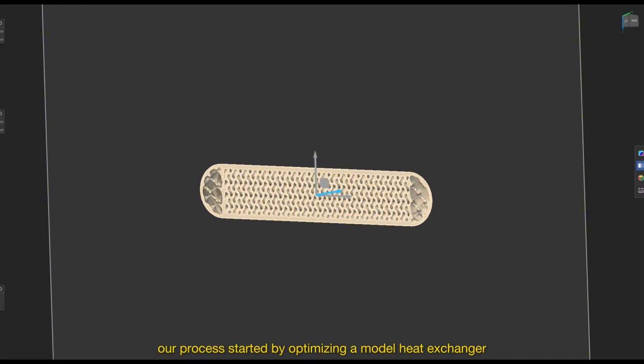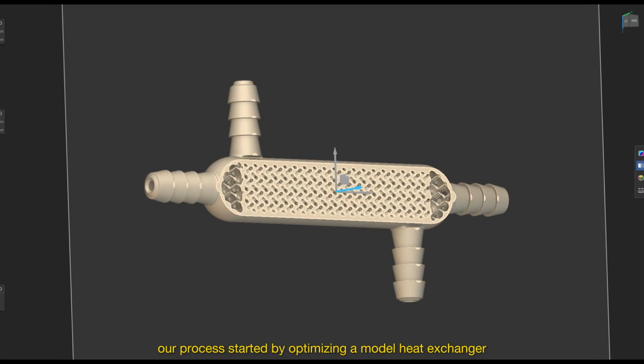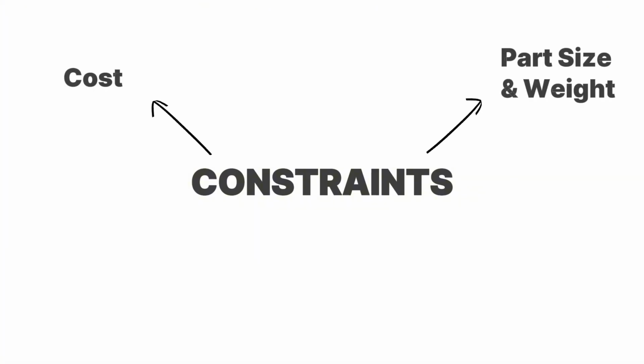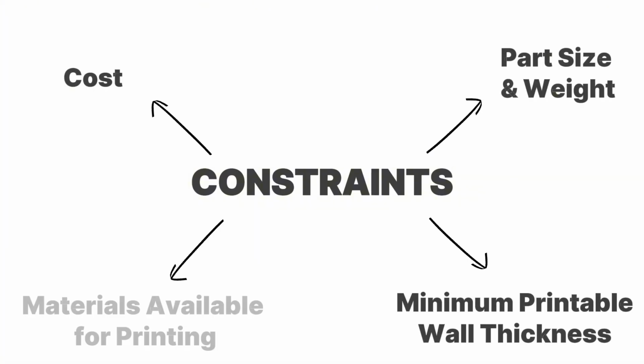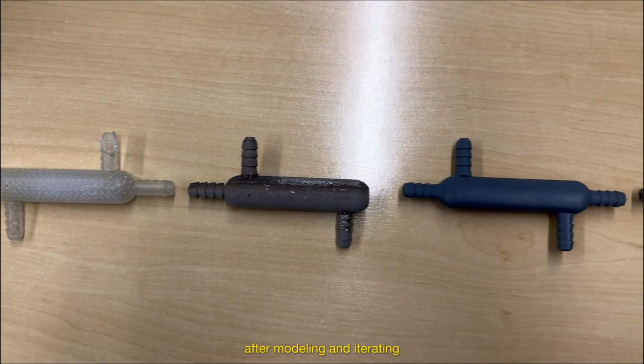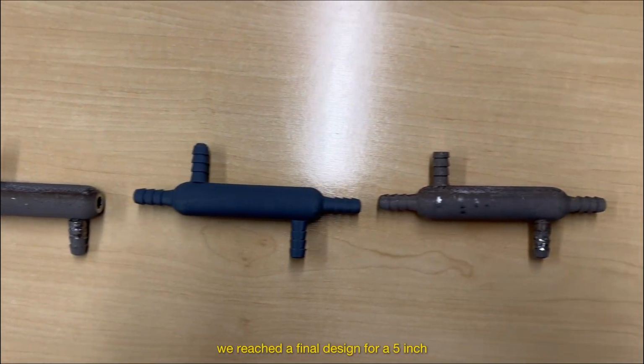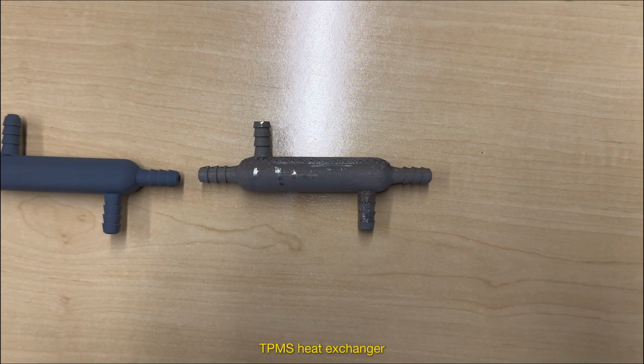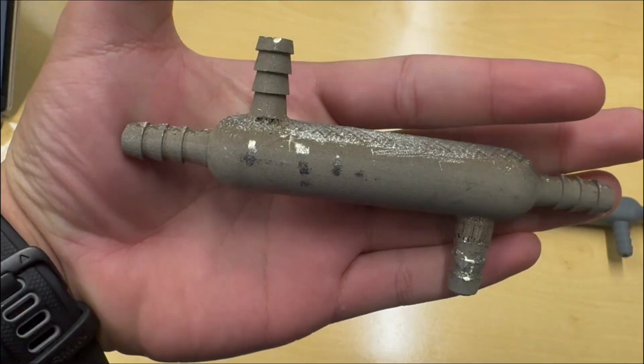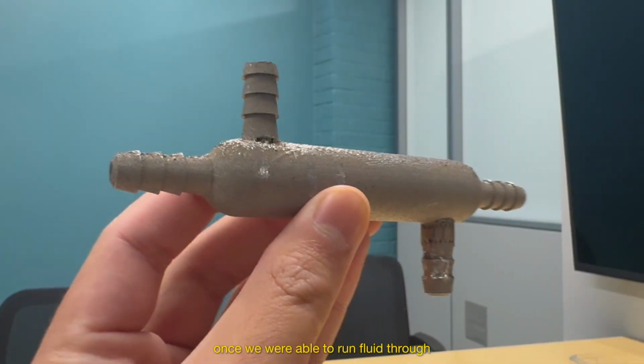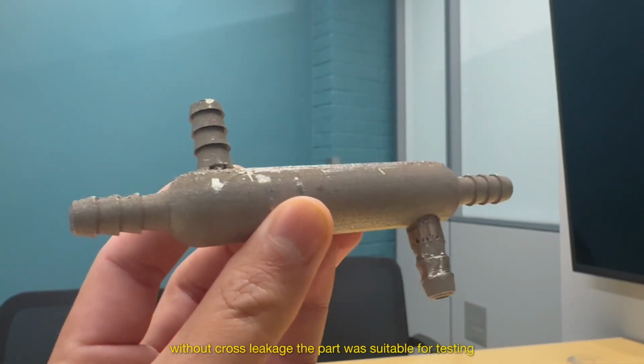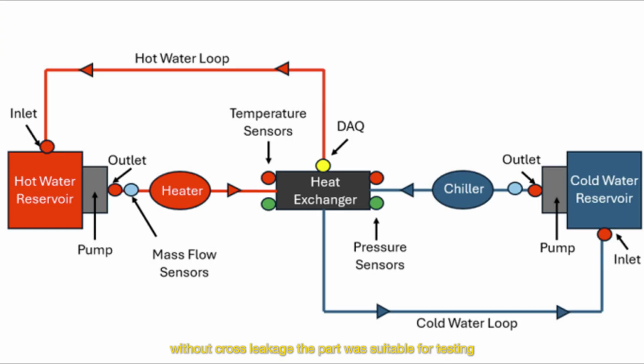The process started by optimizing a model heat exchanger. We accounted for real-world constraints like cost, part size and weight, minimum printable wall thickness, and the materials available for printing. After modeling and iterating, we reached a final design for a 5-inch TPMS heat exchanger, printed in 316 stainless steel. Once we were able to run fluid through without cross-leakage, the part was suitable for testing.